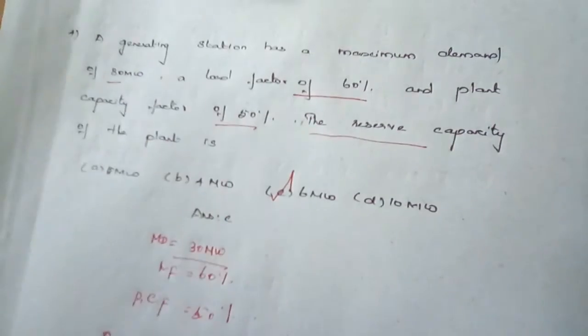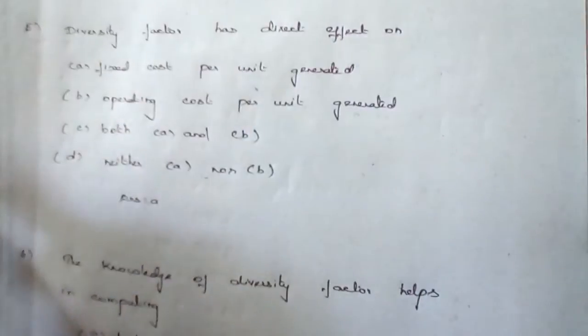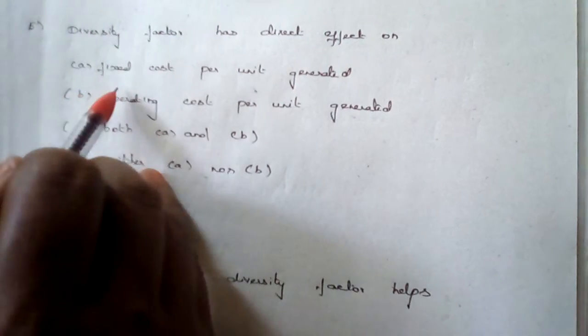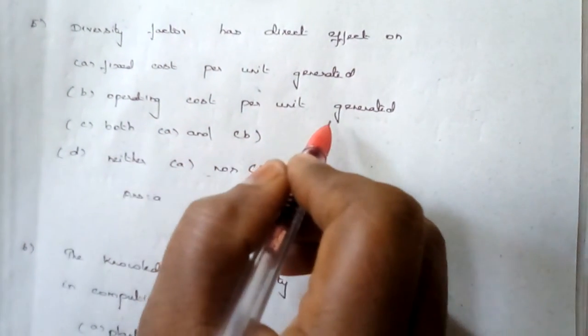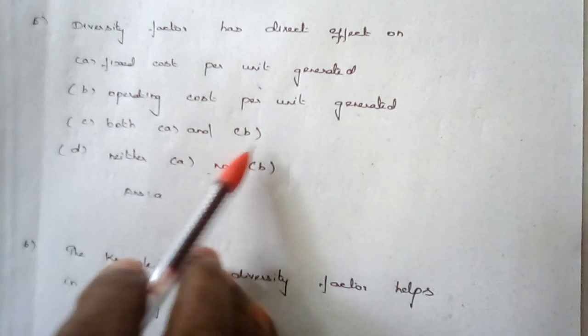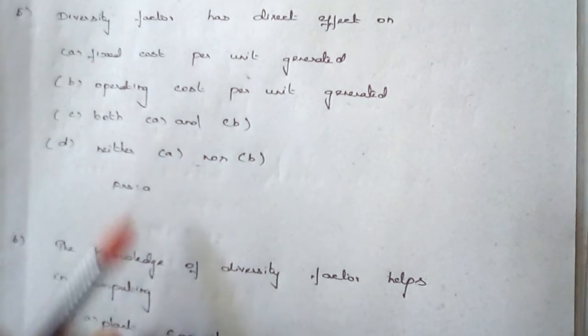We have discussed finding load factor, average load, maximum demand, plant capacity factor, and reserve capacity. Additionally, the diversity factor has a direct effect — the diversity factor must always be greater than unity, and it has a direct effect on the fixed cost per unit generated. That is the correct answer for question number five.